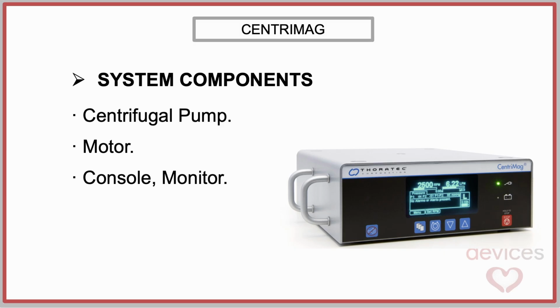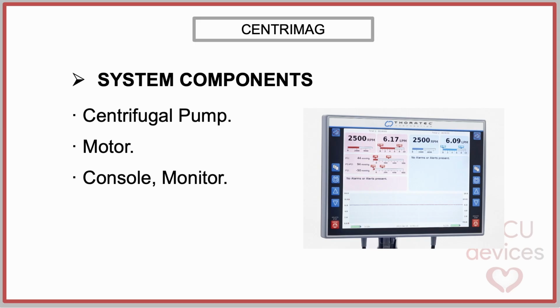Pump speed is controlled through the console, which adjusts rotor rotation to achieve the desired flow. The CentriMag system includes a bedside monitor that provides real-time visualization of key operating parameters, serving as the primary interface for continuous clinical assessment. This display is integrated with a console and is designed to present essential information in a clear and accessible format at the point of care.